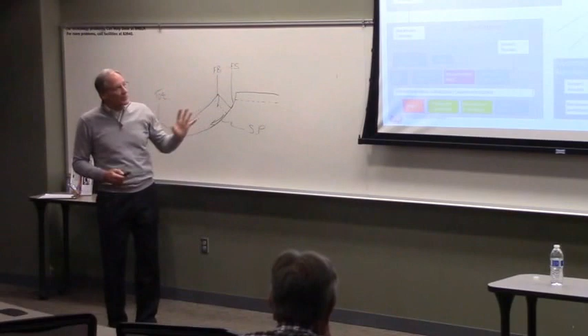Here we have capacitor banks and voltage regulators to support the logic of integrated volt-var control, which again could be up here or at the substation level, either one. So this is what I mean by thinking of the big picture. Don't just think about a relay in the substation, but that relay is part of a larger scheme here, and that larger scheme provides much more value to the utility.